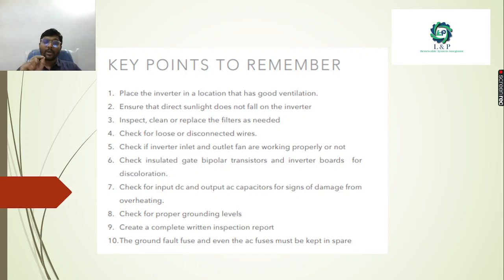Okay, and most importantly, check the insulated gate bipolar transistors and inverter boards for discoloration. Check the input DC and output AC capacitors for any signs of damage from overheating. Check for proper grounding levels and create a complete written inspection report. Again, the ground fault fuse and even the AC fuses must be kept in spare. Also make sure your PV module cables are properly tied with cable ties.